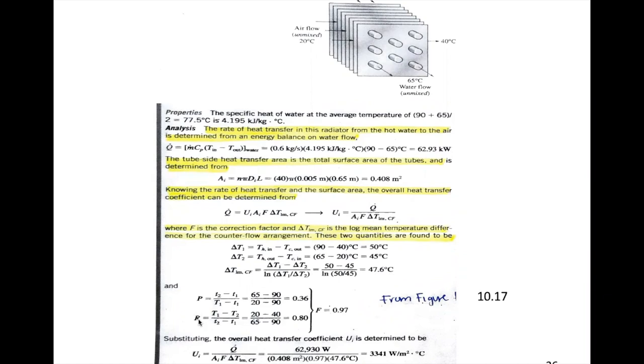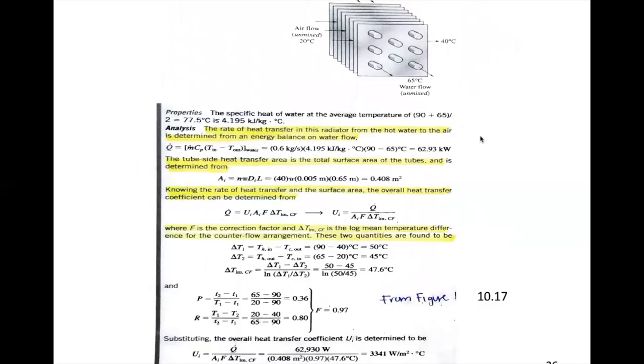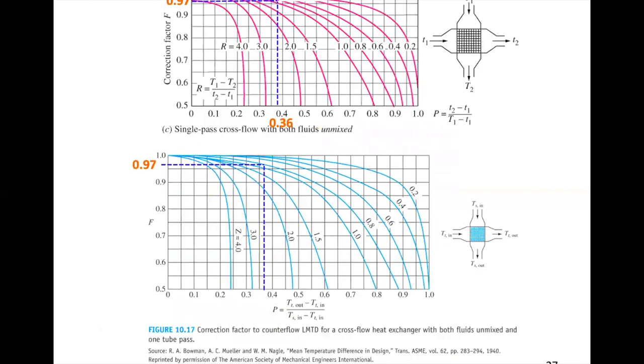We need to calculate P and Z (called R in some textbooks) to read the correction factor from figure 10-17 — the correction factor for a cross-flow heat exchanger with both fluids unmixed and one tube pass. Both fluids are unmixed because we have fins; the fins direct the fluids and prevent mixing. P is (T_tube,out minus T_tube,in) divided by (T_shell,in minus T_tube,in), giving 0.36. Z is (T_shell,in minus T_shell,out) divided by (T_tube,out minus T_tube,in), giving 0.8.